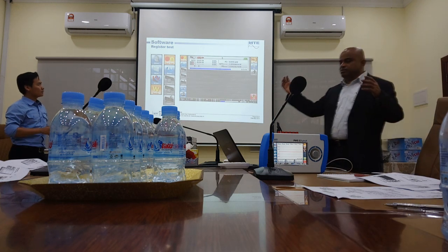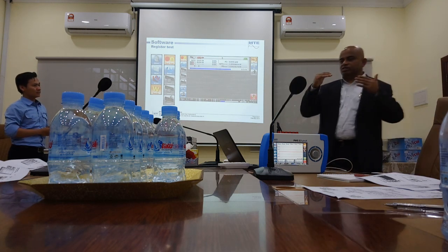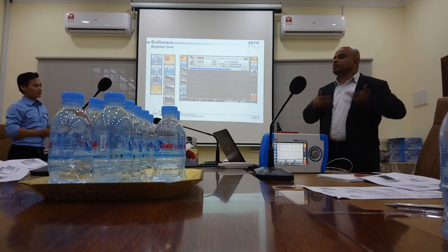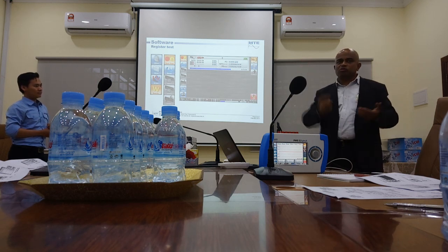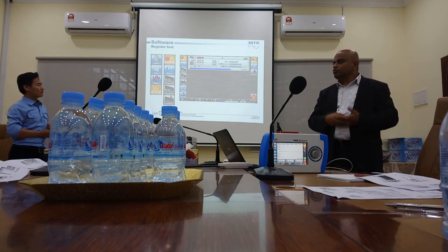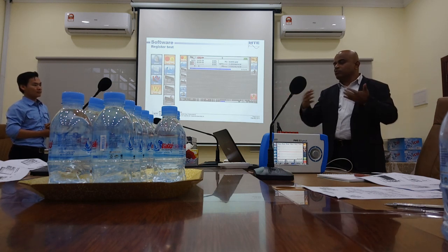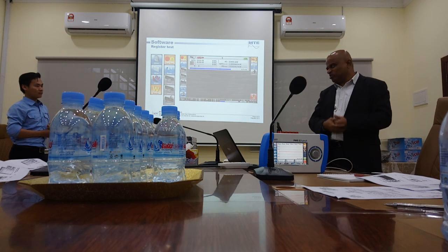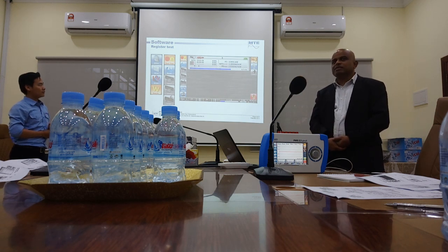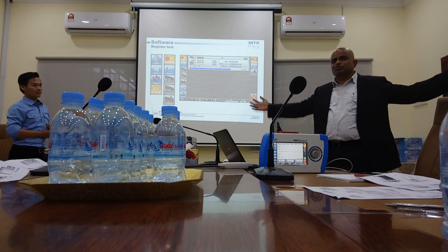See, the problem is, if the customer load is very low, your error is very high, because it is too small a value. So if you calculate, the error may be 10%, which is very bad. So you have to wait at least 1 kilowatt hour, at least 1 kilowatt hour. So you may need to wait for very long sometimes.